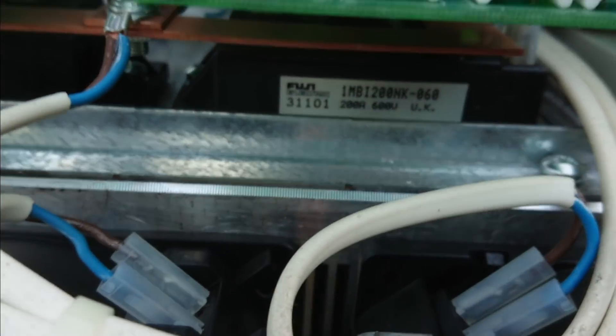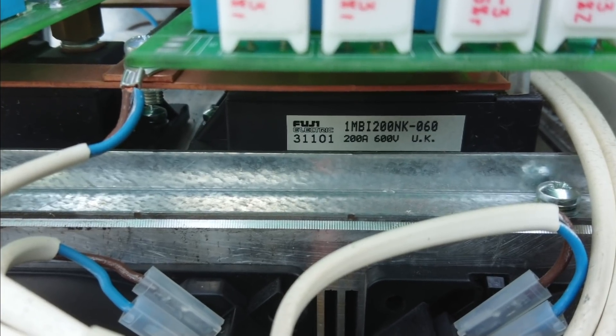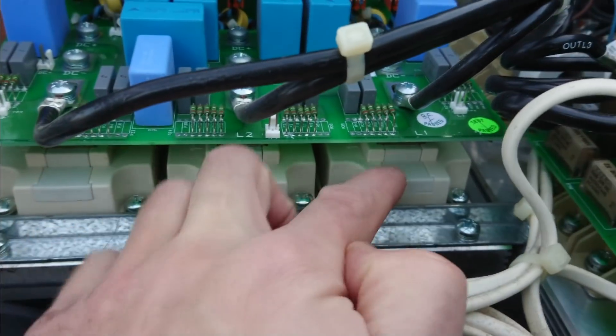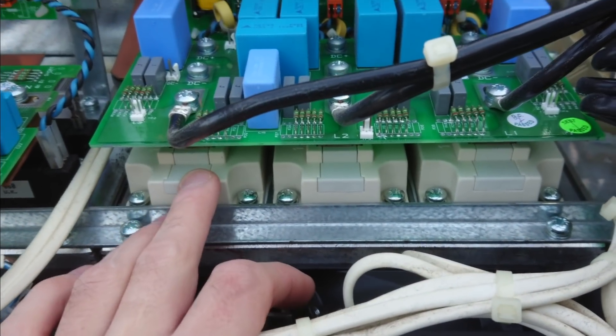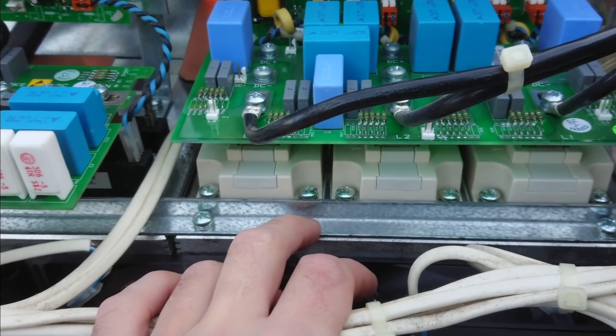If we get down here, we can see that the intermediate inverter is MBI 200 bricks, which is 200 ampere at 600 volts. We can't see the marking with the camera, but these are Eupec FF150R12 — so this means these are 150 ampere, 1200 volt IGBT bricks.